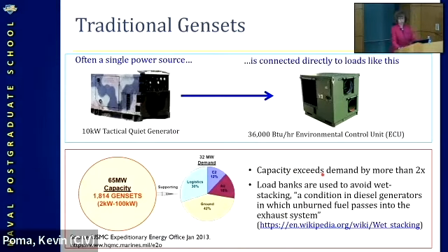So it's not efficient. Second thing is they often carry load banks, which are fake loads - things that dissipate energy on purpose. You add more load to the generator so there is no chance of going into a situation called wet stacking.